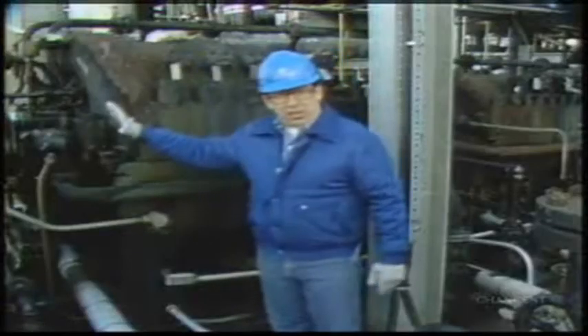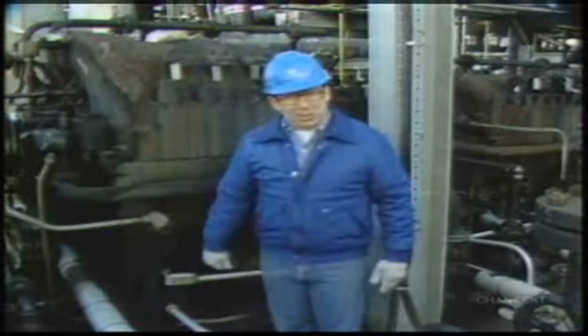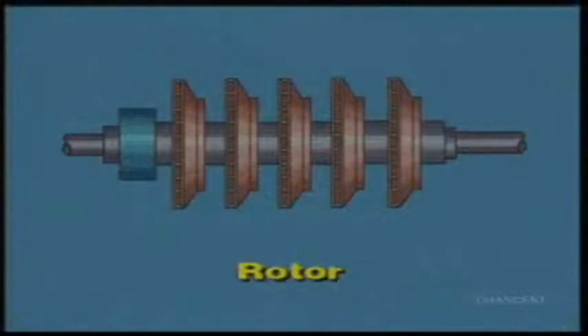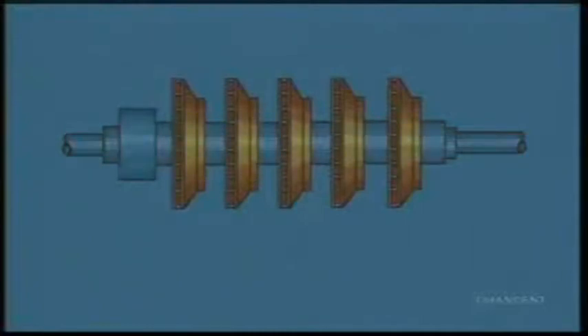Now that we've seen the outside of the compressor, let's take a closer look at the internal components. Inside the casing is the rotor. Rotors usually consist of a solid center shaft with impellers keyed and pressed onto the center shaft. In most centrifugal compressors, rotors are built with a balance piston installed at the discharge end to relieve the thrust bearing load.